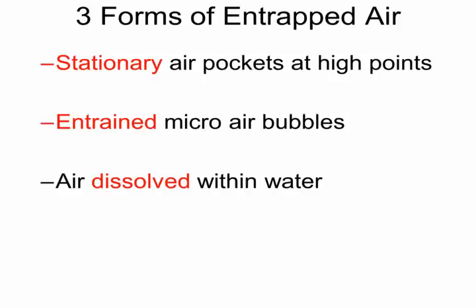So as designers, we want to get rid of all this air regardless of where it comes from, and we need to be knowledgeable that air comes into a system or exists in a system in three different forms. Air that's stationary, basically it forms and goes to high pockets in the system, whether it's the top of a riser or top of a buffer tank as an example. Air that's in the form of microbubbles, and air that is actually dissolved within the water.